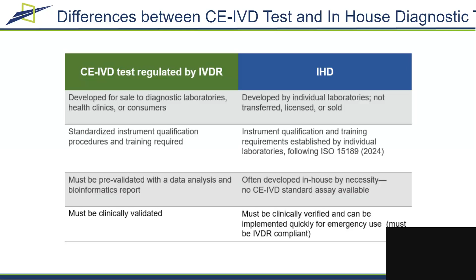But it should follow ISO 15189. At least starting in 2024, that will be a requirement. Right now, it's a recommendation. They're often developed in-house by necessity because there is no CE-IVD test available for what they need. And these IHDs must be clinically verified by running them on known patient diagnoses and can be implemented quickly for emergency use.